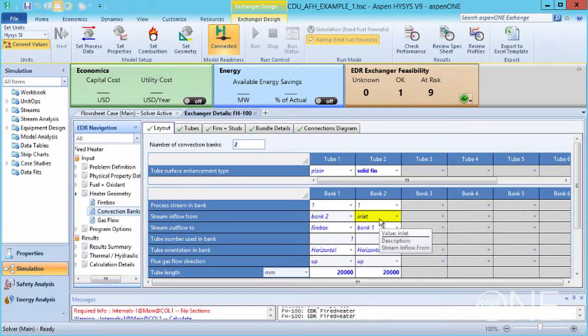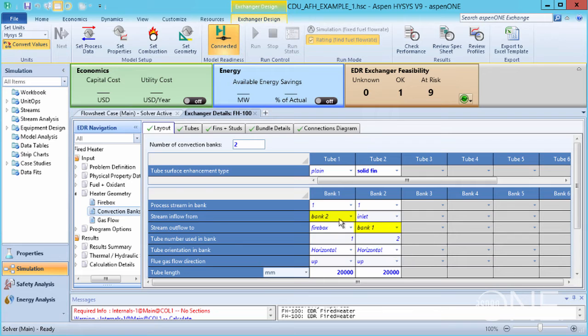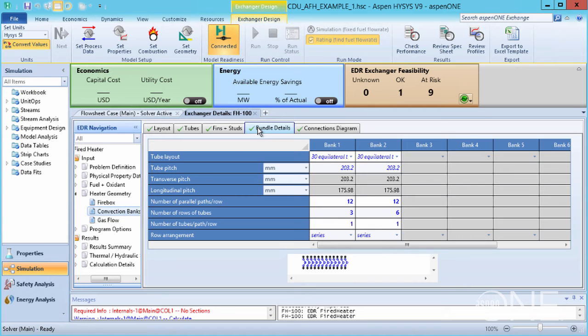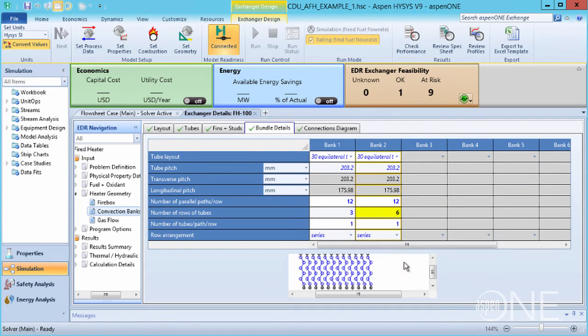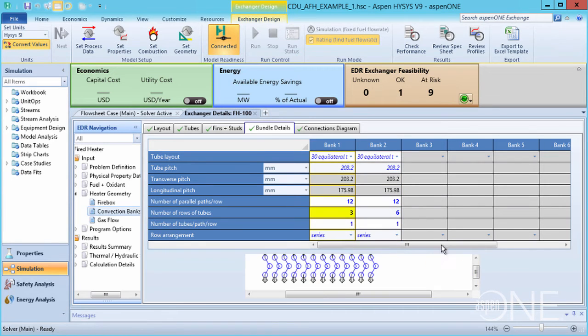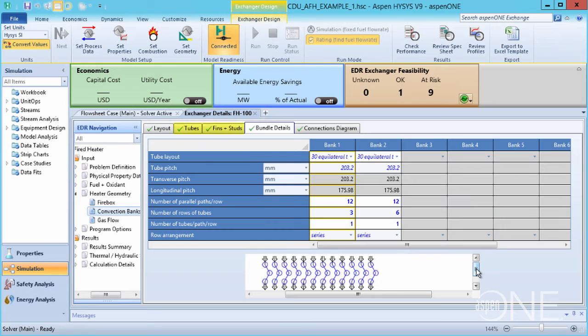The process stream then flows from bank 1 into the firebox. If we go to the Bundle Details tab, we can see how the tubes are arranged in the convection bank. Bank 2 consists of 6 rows, and bank 1 consists of 3 rows of tubes. You may like to look at some of the other tabs where the precise geometry of the tubes themselves are defined. Fired Heater has a thorough list of geometry options that you can fine-tune to run more accurate rigorous simulations.